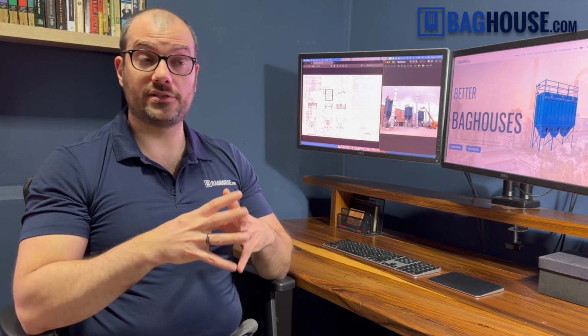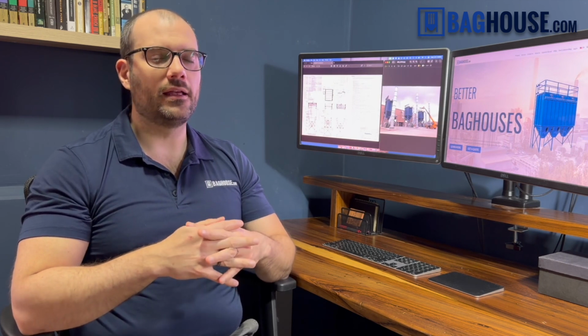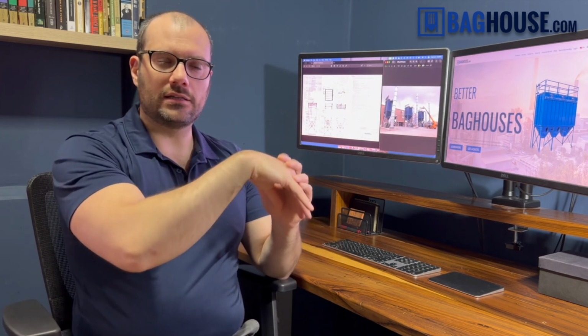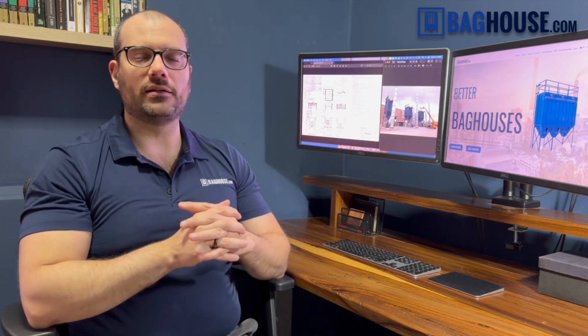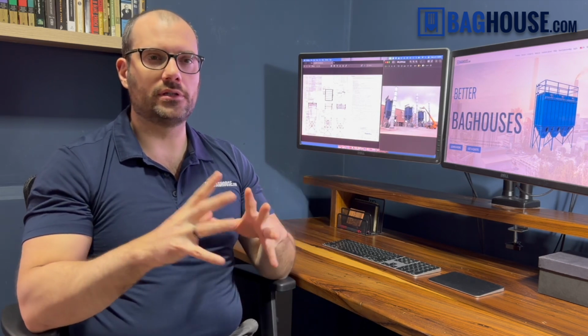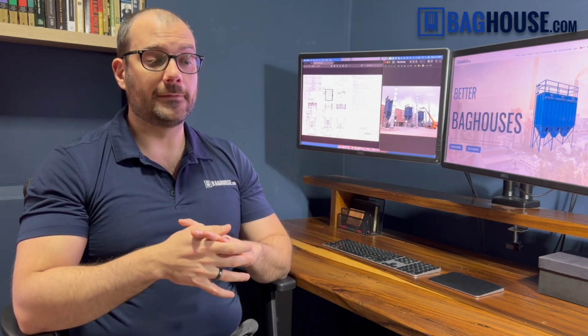We might also identify ways that they can have a more comprehensive approach on multiple systems that makes more sense. So perhaps instead of having so many active systems, perhaps active chemical explosion isolation or active sprinkler systems, they might be able to switch to more passive systems like isolation valves, CO2 systems. They don't require constant recharging, inspections, annual inspections, things like that. So when we go through, we're always looking for the practical on the operations side, but the fire safety, combustible dust stuff, that's always in our minds too. And we're able to give a comprehensive thing. Because many times, fixing a practical problem removes a problem from combustible dust.